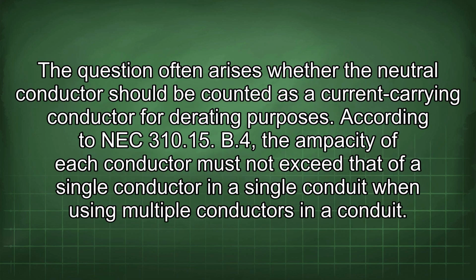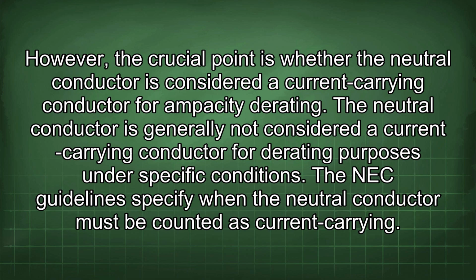The question often arises whether the neutral conductor should be counted as a current carrying conductor for derating purposes. According to NEC 310.15(B)(4), the ampacity of each conductor must not exceed that of a single conductor in a single conduit when using multiple conductors in a conduit. However, the crucial point is whether the neutral conductor is considered a current carrying conductor for ampacity derating. The neutral conductor is generally not considered a current carrying conductor for derating purposes under specific conditions.